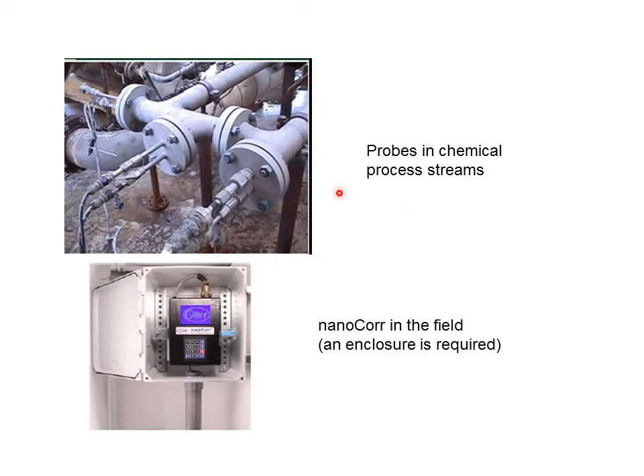This is an example of the CMAS probes in a chemical process stream. As we can see here, the probes are in the chemical process stream through a fitting, an MPT fitting. And the nanoCorr is in an enclosure required for field use. In some cases, for intrinsically safe field use, the nanoCorr must be placed in an explosion-proof container.